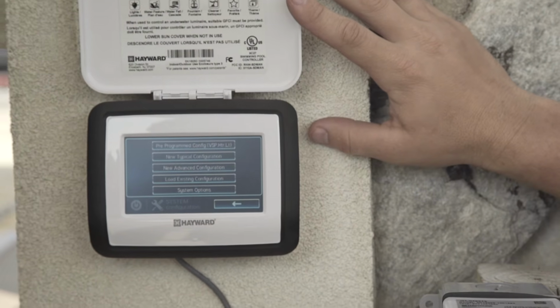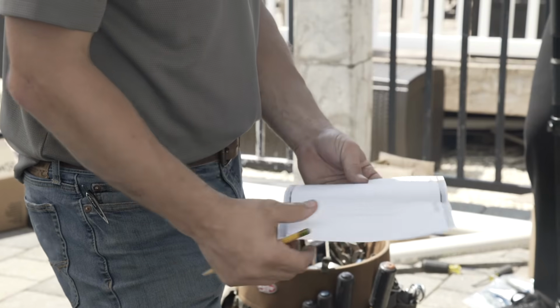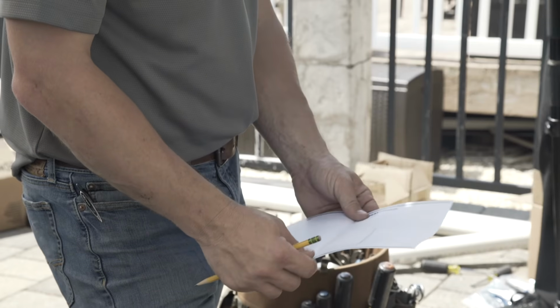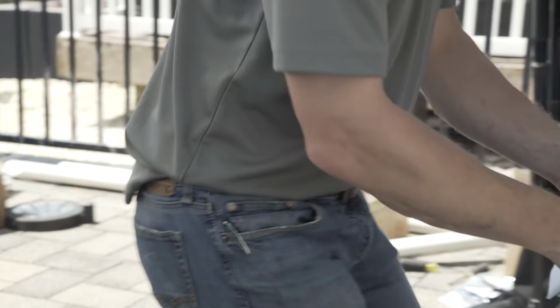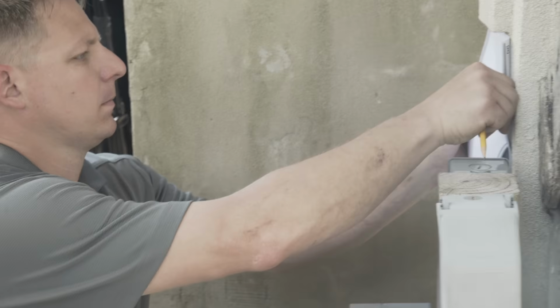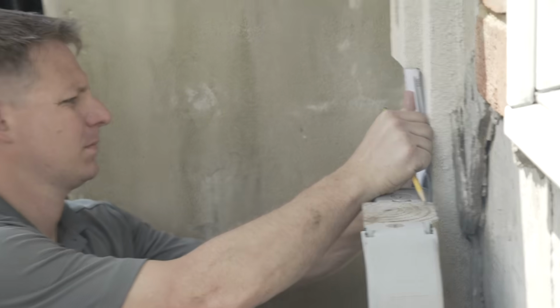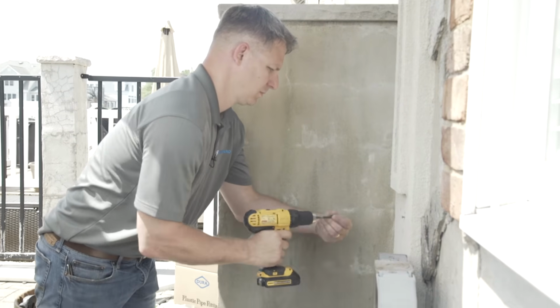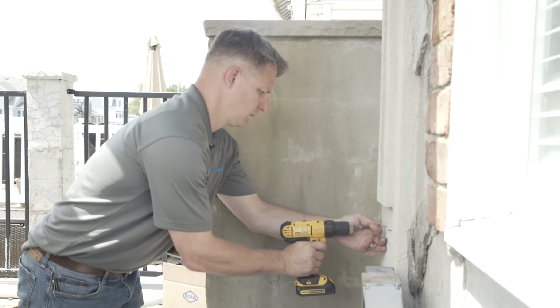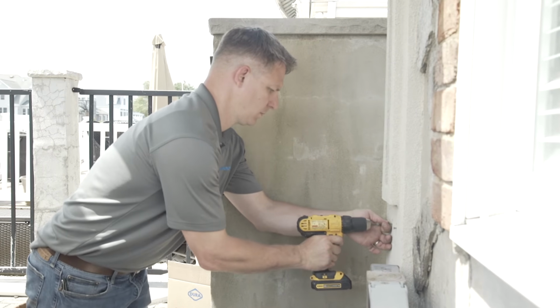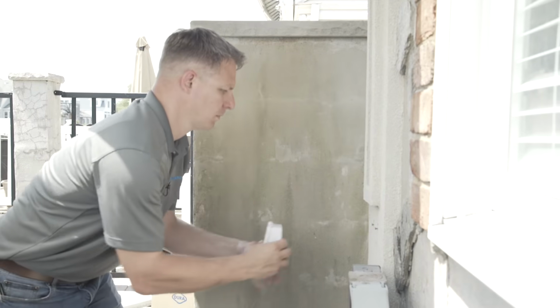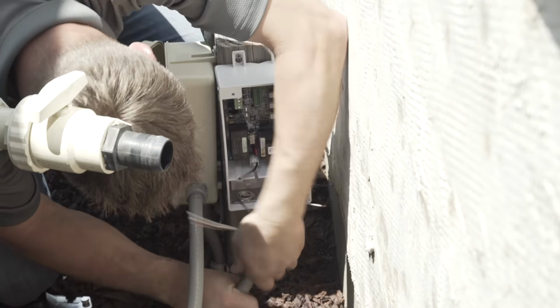The controller has 2 keyhole cutouts on the back of its enclosure. To mount the controller, use the template provided in the installation manual to scribe 2 marks. Then, screw the 2 provided fasteners into the mounting surface. Note: to achieve a tight fit, leave 1/8 inch gap between the base of the screw head and the mounting surface, adjusting as needed.